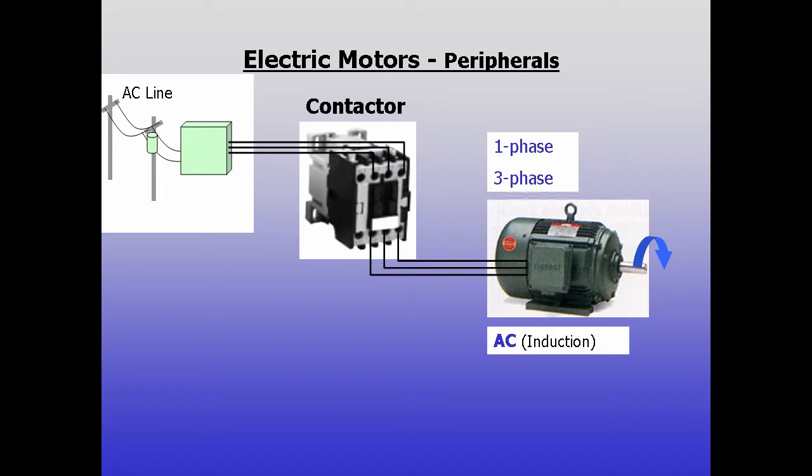Contactors, by definition, are rated for inrush currents. They can be used with single or three phase motors, although most are built with three poles for three phases.